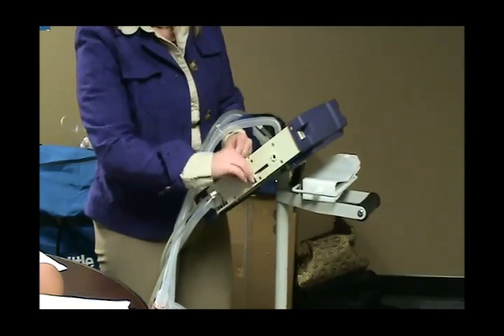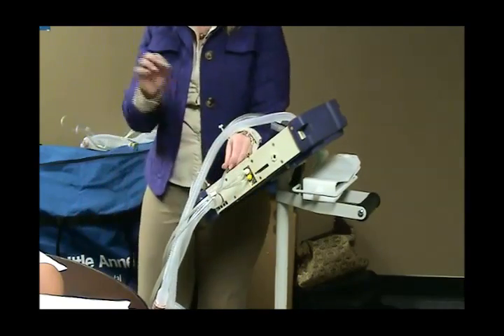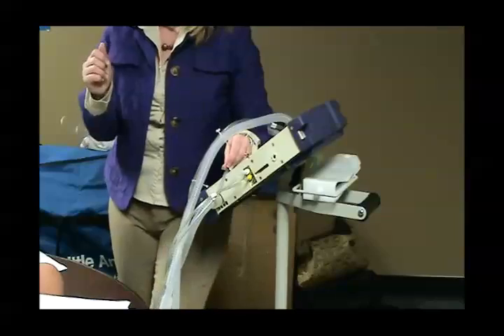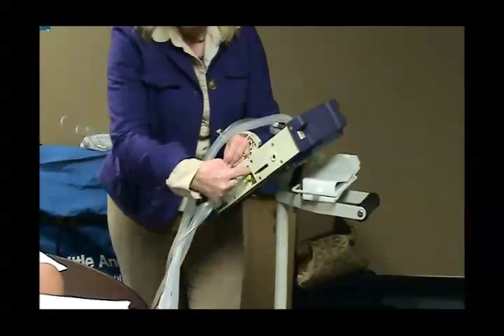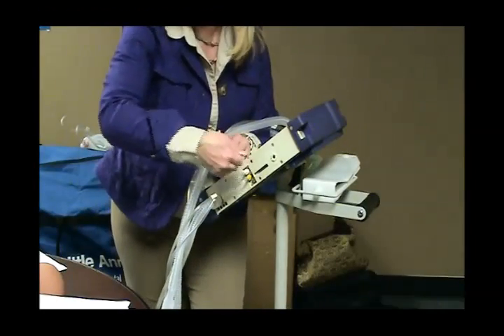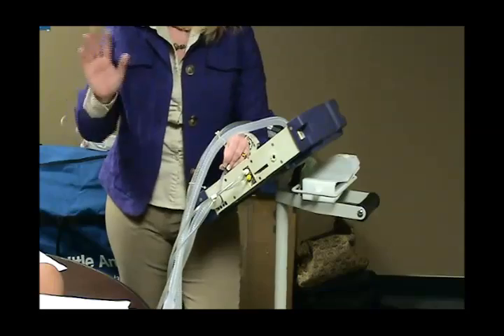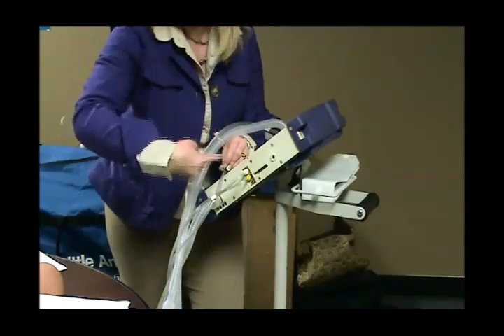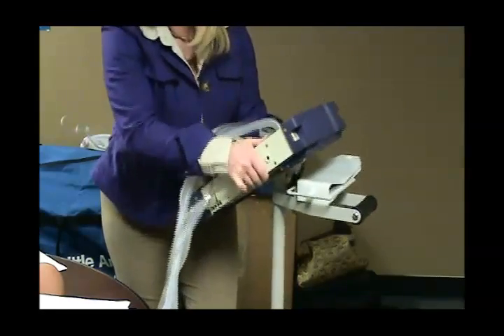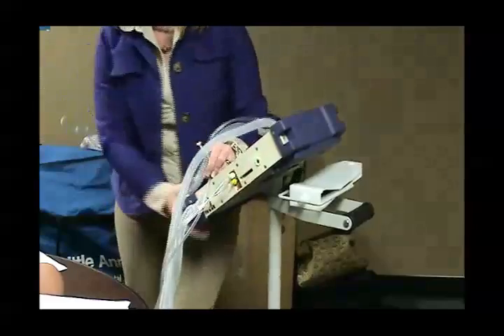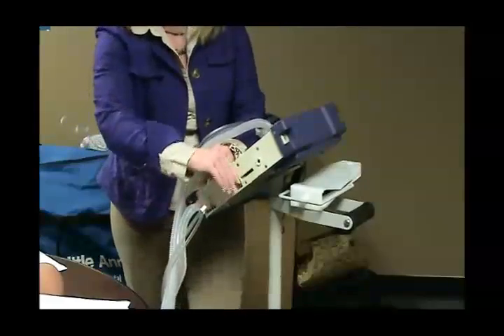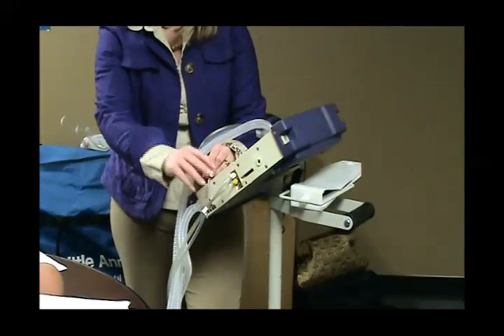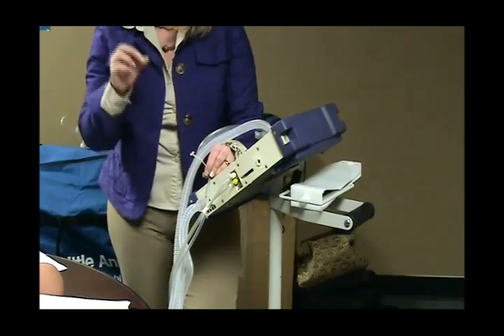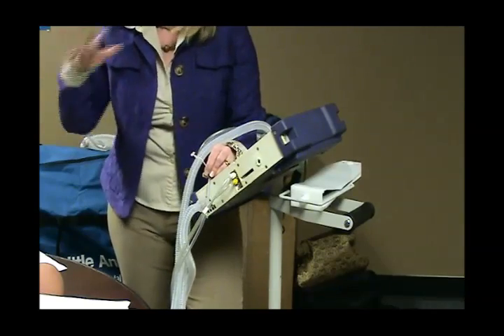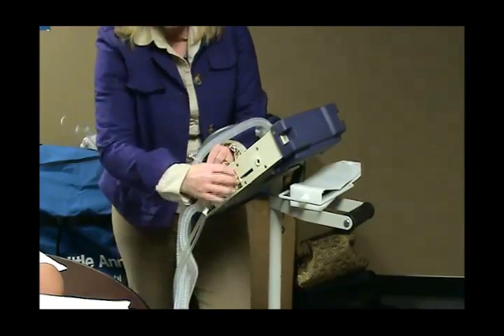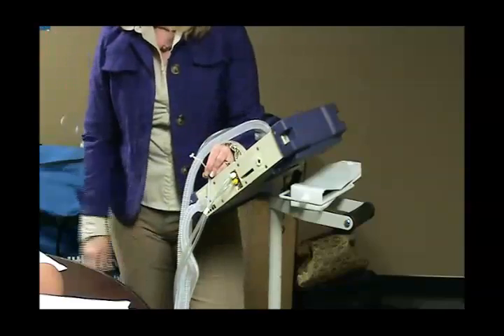The reason you want to do that is these are Luer locks, but unlike your IV tubing, the outside does not spin. So if you plug it in and then tighten it down, if you don't do that little trick, it'll work, but the tubing will be torqued. And then when you take them out to the living room and you go out to the porch, after a while these are going to shake themselves loose, and you're going to get disconnect, low pressure alarms, all kinds of crazy things going on, okay? So do that one little trick, and I'll save you lots of time.